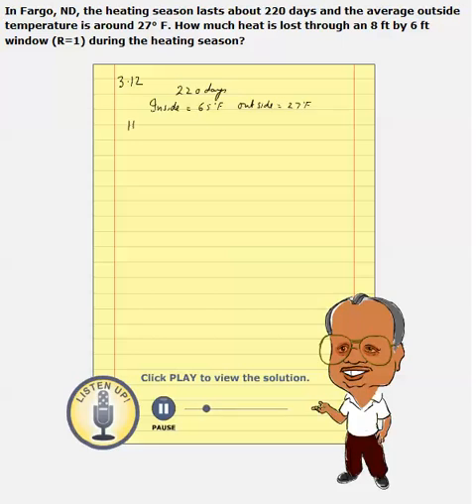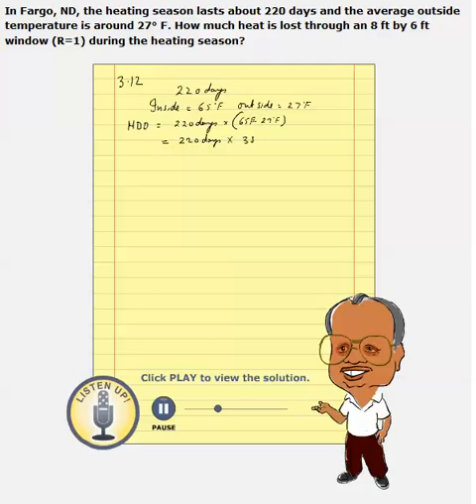Therefore, heating degree days can be calculated like this: 220 days times 65 minus 27 degrees Fahrenheit. That is 220 days times 38 degrees Fahrenheit, which is equal to 8,360 degree days.